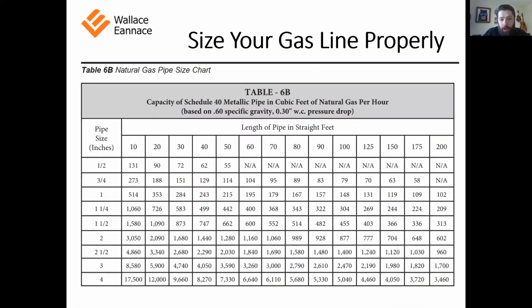Now, if we look at this chart in your I&O manual, you'll see that if you have 100 foot of straight pipe and you go to 1 million BTU, you're actually going to need a 2.5 inch gas connection size, not the 1.25 inches on there, okay? So you want to increase your size right off of the unit. We know it's a smaller connection, and make sure you run that 100 feet in the proper size, which should be 2.5 inches, okay? Oversize is not a problem, but undersize can be a huge issue.